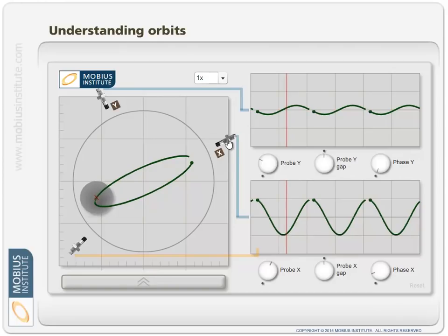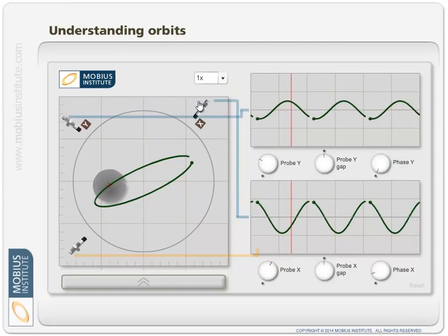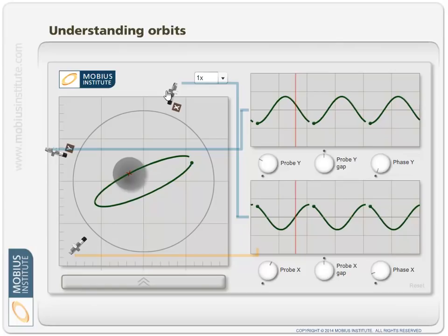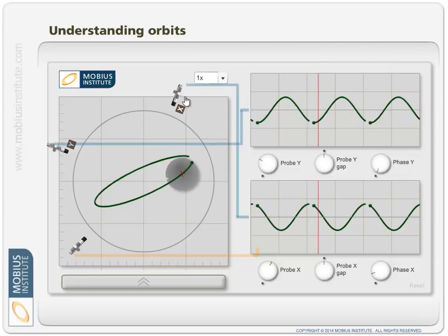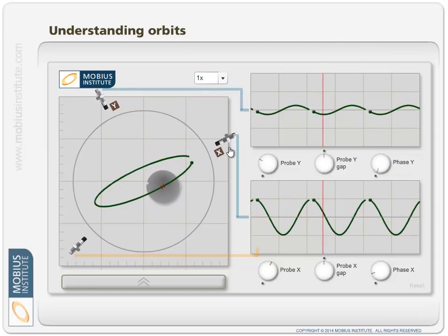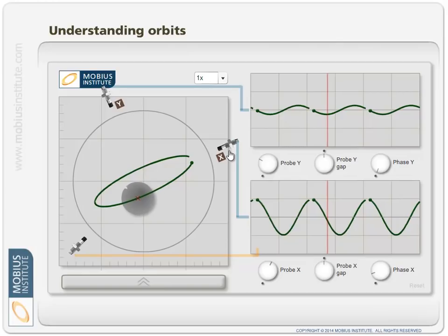Whereas if you watch those two signals and I rotate this around, you can see the amplitudes are lower. So that's just something to keep in mind with your alarm settings and trip settings. If you've got the probe in this direction, you may not trip. If the probes happen to be here, it might trip. Just something to think about. There's a measurement called S-max, which always figures out what that longest axis vibration level is, and you can trip on that instead. Just something to think about.